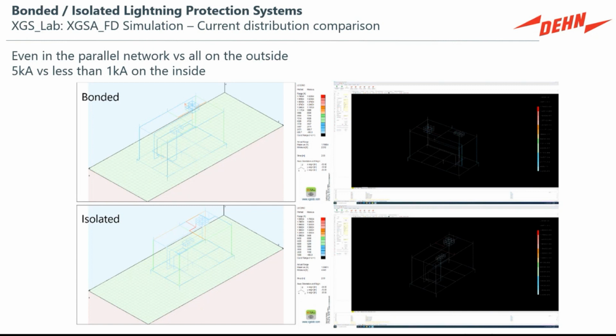Everybody goes up together, everybody's down. There's no voltage difference. It's equipotential bonded. The idea is that if the lightning strikes the building, it doesn't produce sparks and flashover to the other metal bodies within the structure. But what it does do is share some of that lightning current into the electrical grounding system, which can then influence the electrical works within a structure.